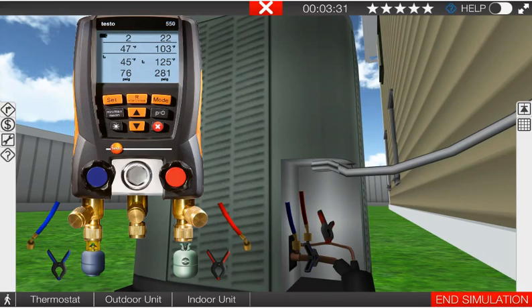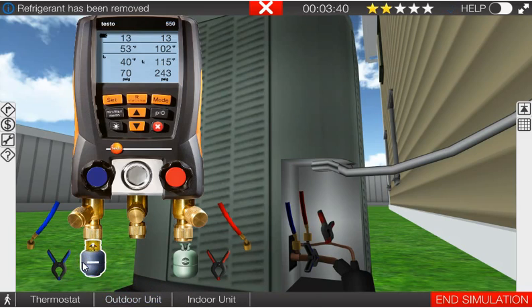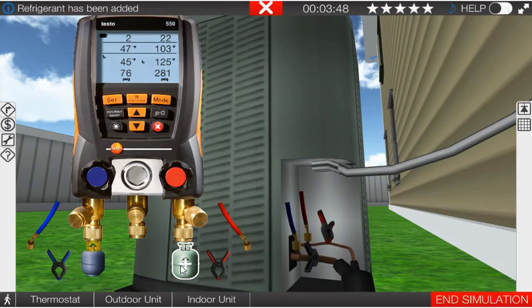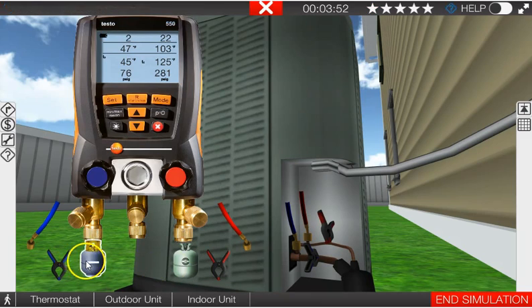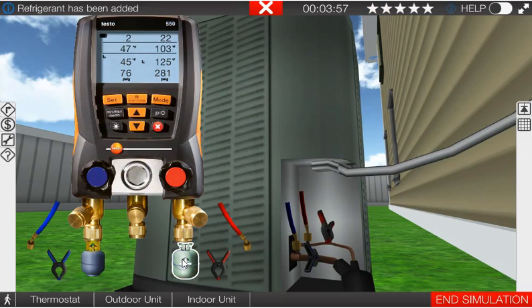So let's go back. 13 and 13 again. Look what happens to the condenser pressure and temperatures as we add refrigerant. The pressures and temperature goes up. Look what happens to the low side when you add more refrigerant. Those pressures and temperatures go up.